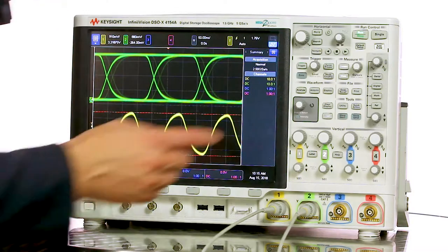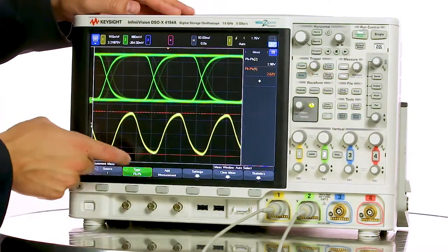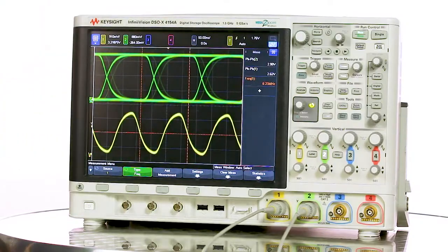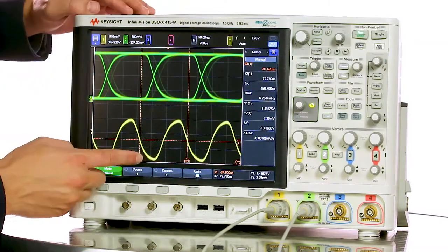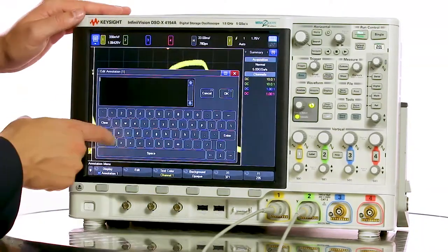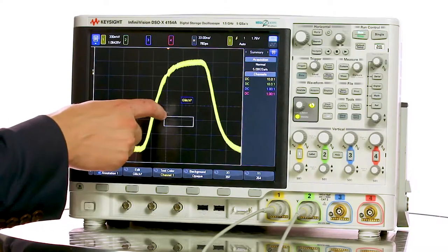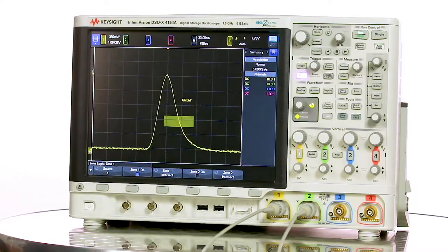One of my favorite things about this scope is the 12.1-inch capacitive touchscreen, which gives you some really useful touch functionality. You can quickly navigate through menus, adjust your signals, move cursors, and type in annotations and numerical values. You no longer have to type with the knob like you're entering a high score in an old arcade game. You can also zoom in on an area of the screen or even set up a zone trigger. Simply draw a box on the signal you want to isolate and the scope will do the work for you.